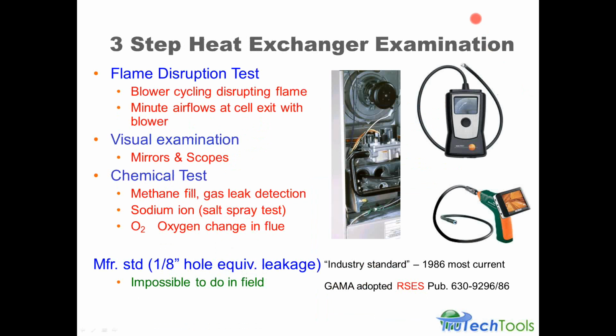On this page, we promised to talk a little bit about heat exchanger examination. Well, there are really three different modes of doing it. One is simply the flame disruption test, where you look to see if the blower cycling on and off disrupts the flame. That means there's communication between the combustion compartment and the distribution air side when there should not be any. If that happens, then there's likely a problem with the heat exchanger that's blowing the distribution air into the combustion compartment, and that's a bad thing. There's a breach in there that shouldn't be.